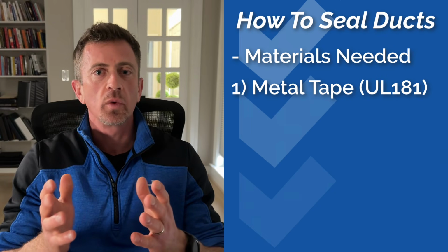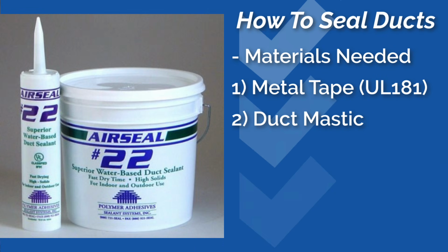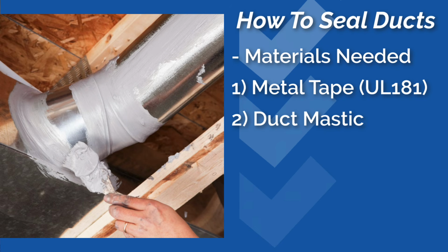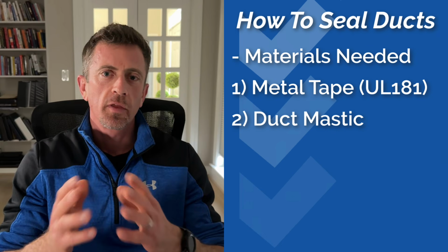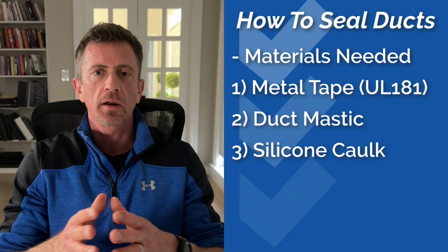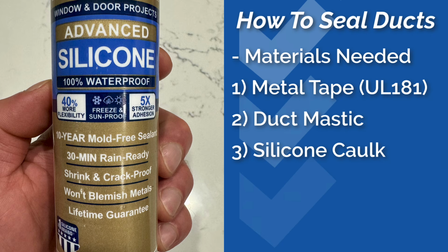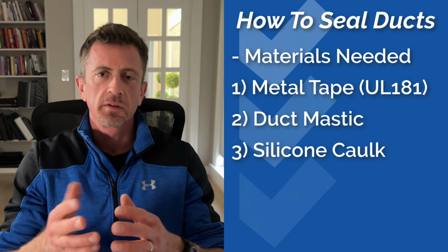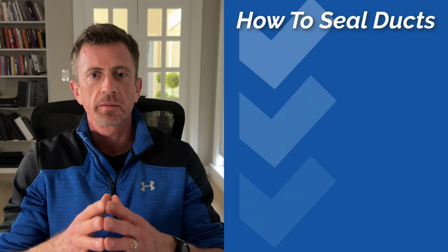The next material that you want is duct mastic. This is your best friend. It's a gooey sealant that's perfect for larger gaps. It's kind of like a wet putty and it comes in gallons, and you paint it on with a 2-inch chip brush. The third one that you're going to use is silicone caulk. This is used for smaller gaps and tight spots, where if you just want to seal a seam together, you can use silicone caulk and it's perfect for that purpose.